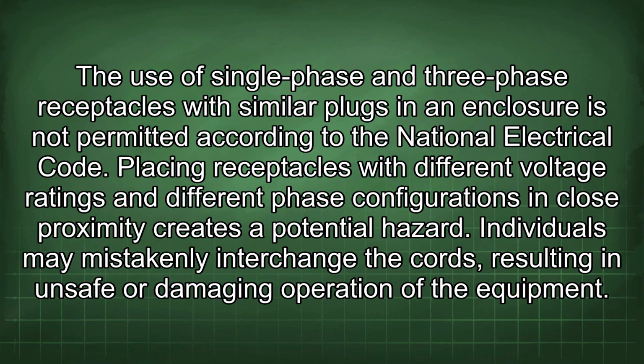The use of single-phase and three-phase receptacles with similar plugs in an enclosure is not permitted according to the National Electrical Code. Placing receptacles with different voltage ratings and different phase configurations in close proximity creates a potential hazard. Individuals may mistakenly interchange the cords, resulting in unsafe or damaging operation of the equipment.